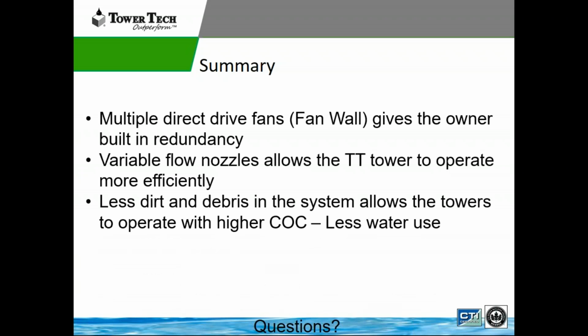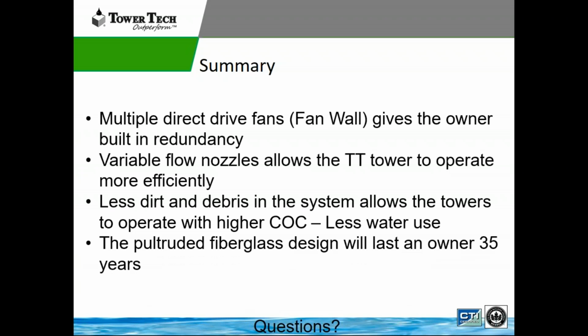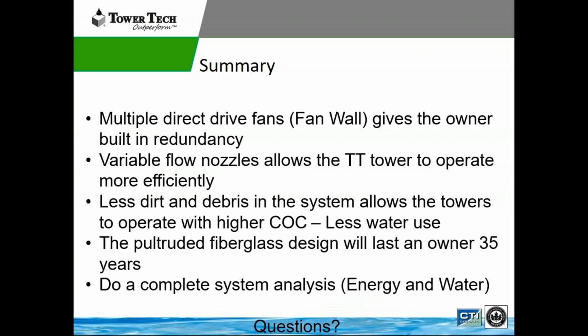Again, we have less dirt and debris in our system, which allows the tower to operate with higher cycles of concentration, which allows us to use less water, which in Chicago, as we mentioned before, is a very big deal, okay? And then the pultruded fiberglass design will last an owner 35 years. So those are all big things. And the last piece, do a complete system analysis, and any one of your folks from TEC will help you. And if they can't, I will help them do a complete analysis on the water-cooled system itself.